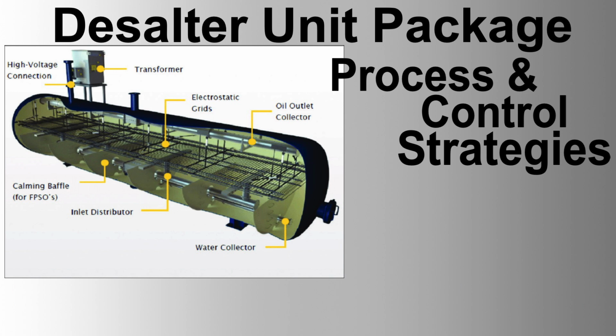4. Water quality. Ensure the quality of the injected water is maintained to prevent scaling and fouling of the desalter equipment. 5. Electrostatic field maintenance. Check and maintain the electrostatic field system, including power supplies and voltage controllers, to ensure consistent performance. By following these procedures and maintaining the equipment properly, the electrostatic desalter can operate efficiently, removing impurities from crude oil and protecting downstream refining processes from corrosion and fouling.